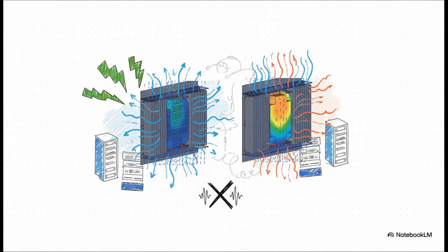This is a great example of hardware innovation. Engineers used fluid simulations and found that the tightly packed fins on a normal air-cooling heatsink actually block the flow of liquid. So they designed a new heatsink with fins that are thicker and spaced farther apart, specifically for liquid cooling. The result: a 1.24 times improvement in cooling performance.